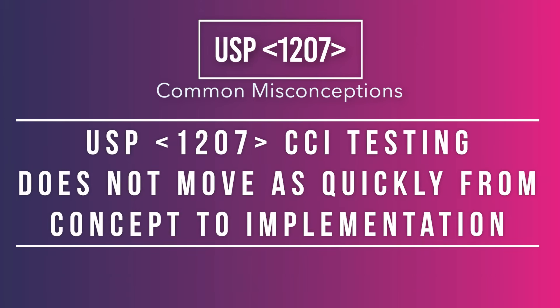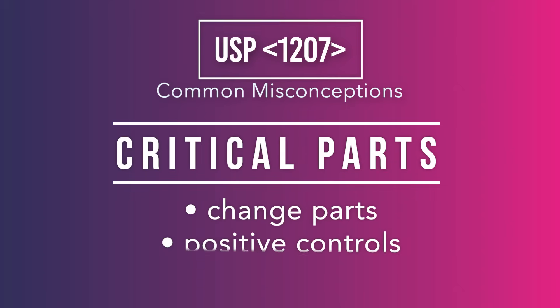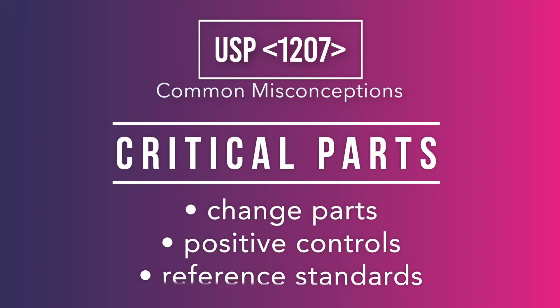It is generally assumed that USP 1207 testing will be quickly implemented and completed — this is not the case. There are three critical parts of a successful CCI program that impact the time schedule: change parts, positive controls, and reference standards.